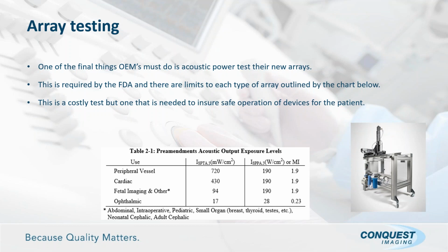So guess what happens? If they design an array, let's say a vascular array for use in vascular imaging, and it exceeds 720 milliwatts per centimeter squared, they have to go back to the drawing board and figure out, okay, now we've got to do a redesign, rework to get that down below that level. That is the one thing that the FDA is very stringent on, is power output for arrays. So again, the OEMs have to do this. It's required. I personally think it's a good thing. And, you know, they've got to make sure it's going to be safe. But I can tell you this cost is in the thousands and thousands of dollars to do these power tests. And it's just another thing that gets added to the equation with the final cost.